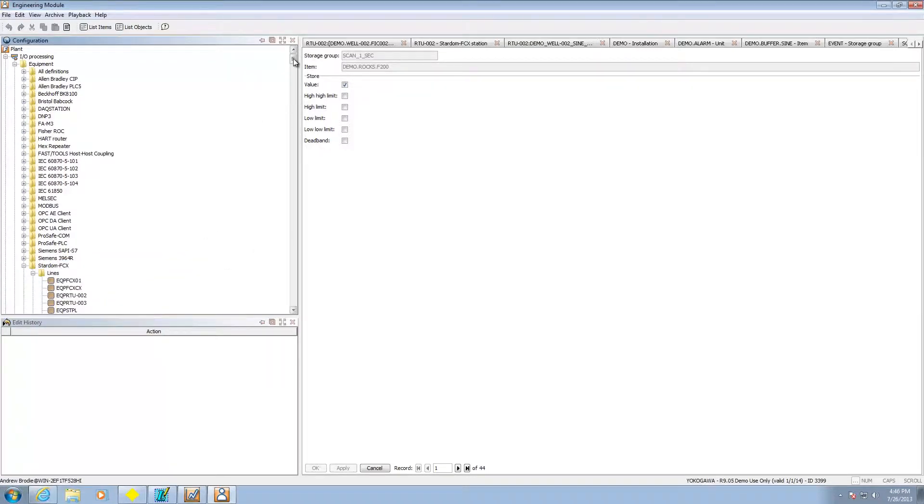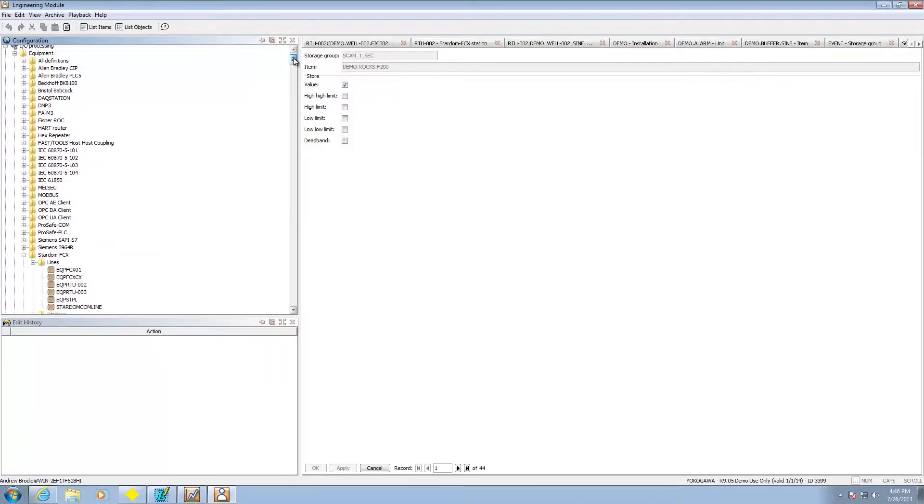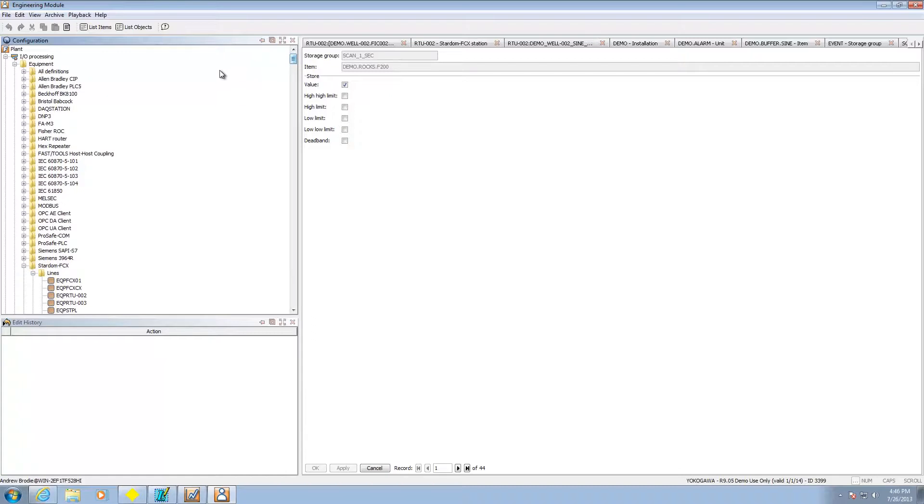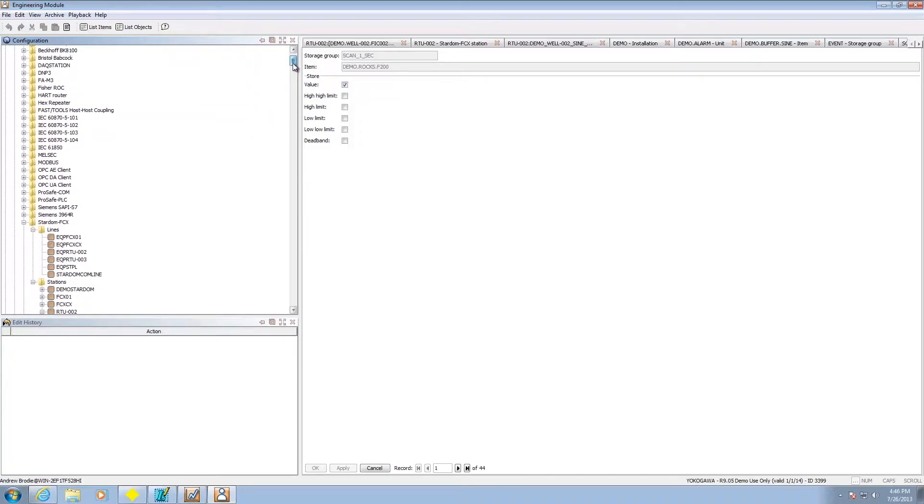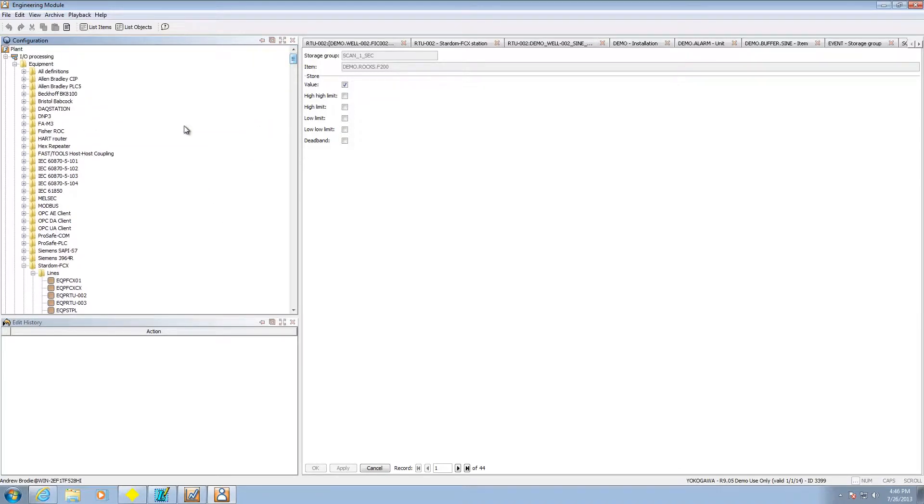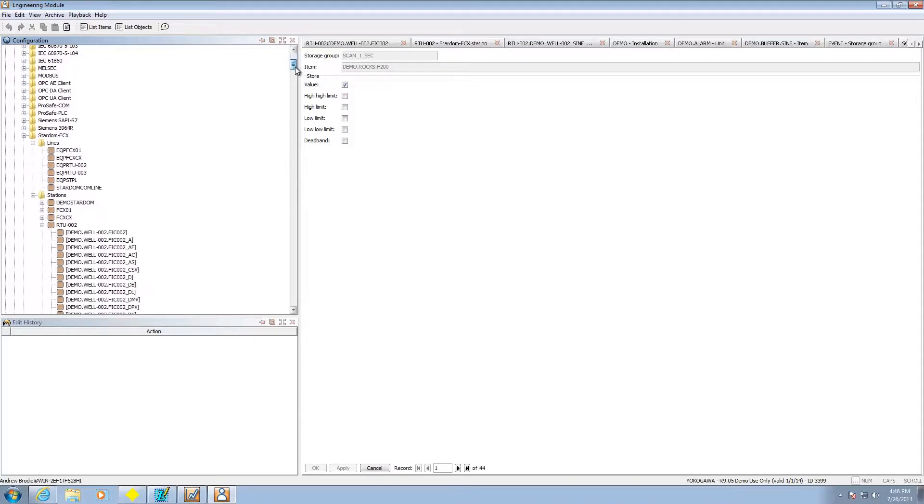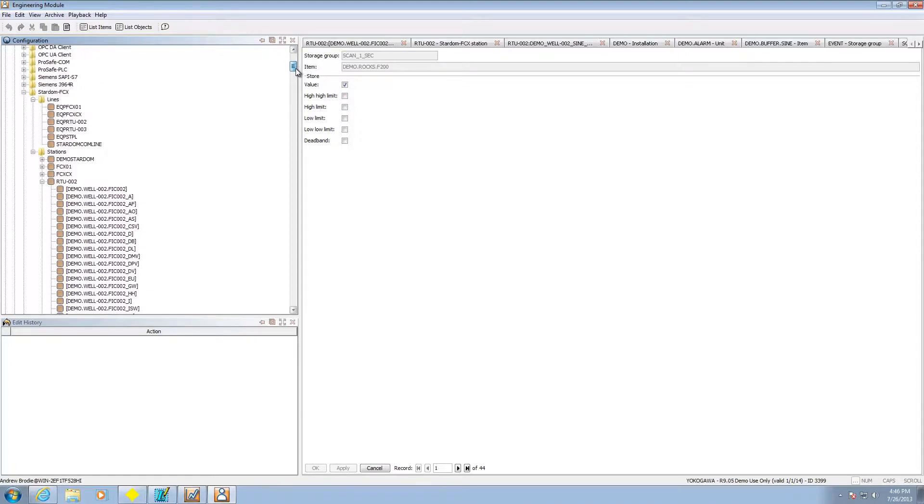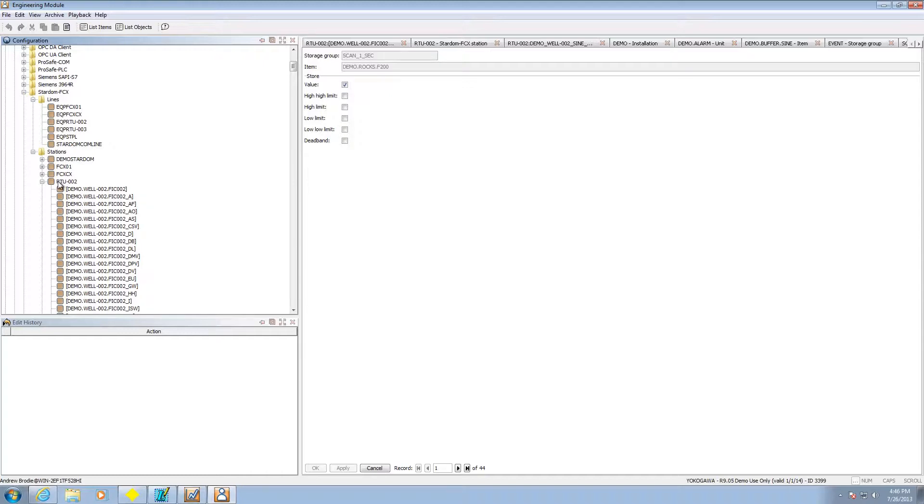The setup is fairly linear from top to bottom. First thing you're going to do is set up your communications to the equipment. That consists of setting up a line. This is essentially the communication pathway to the particular unit you're talking to. Then next is station. This is actually the particular unit on your communication line. And then the last thing you're going to do under each station is set up the items.